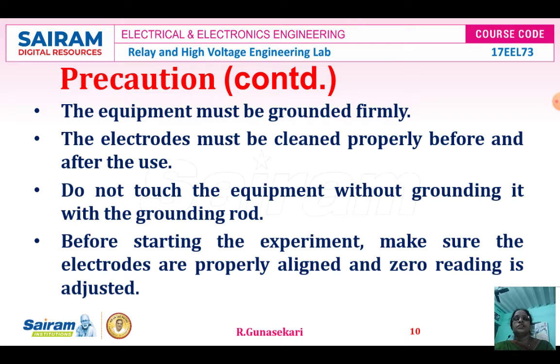The equipment must be grounded firmly. The electrodes must be cleaned properly before and after use. Don't touch the equipment without grounding it with the grounding rod or discharging rod. Before starting the experiment, make sure the electrodes are properly aligned and zero reading is adjusted.